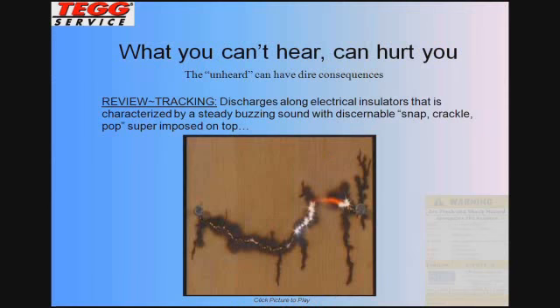Moving on to tracking, it's very similar to arcing in nature. What I mean by that, tracking gets referred to as baby arcing because there are discharges of electricity that occur along insulating materials that aren't supposed to be conductors. And when these discharges occur, there's usually carbon trails that are left behind as visual evidence. But using the ultra probe as a safety mechanism or a first line of defense, we wouldn't traditionally have a line of sight to what we are interested in. So the carbon trails may not be visible.